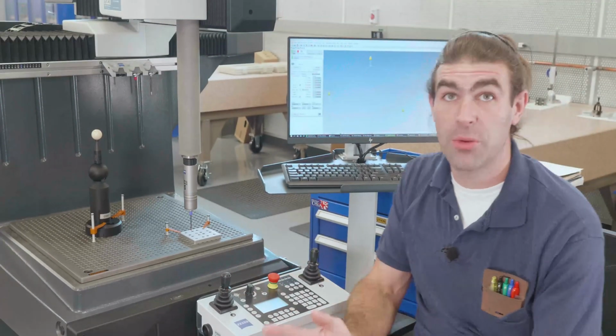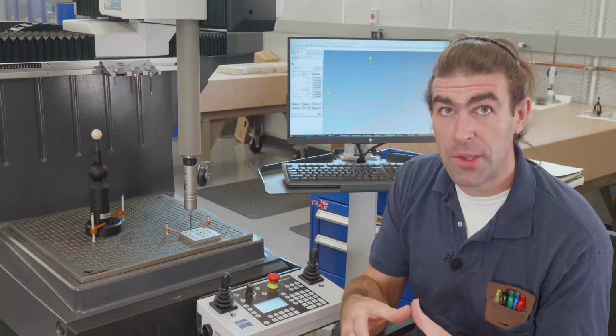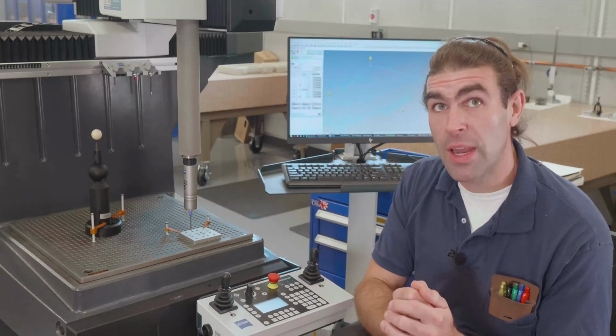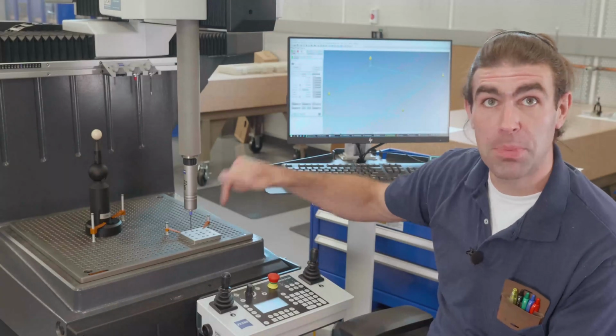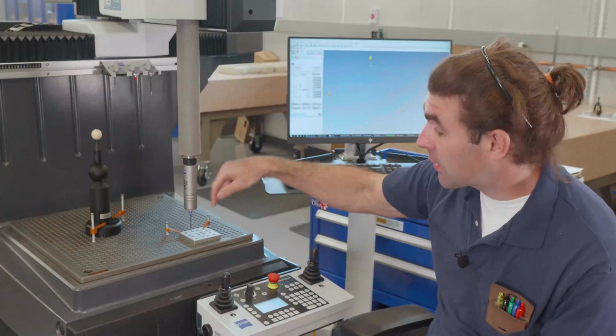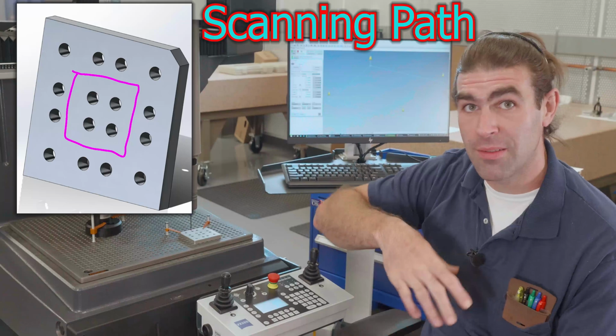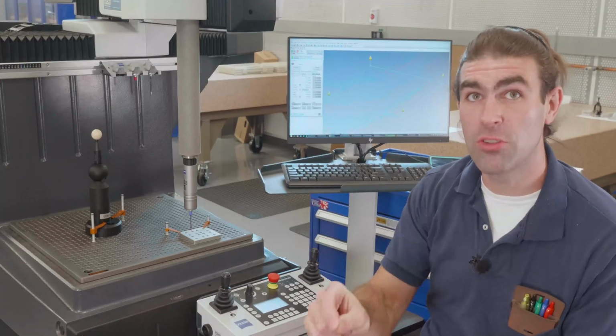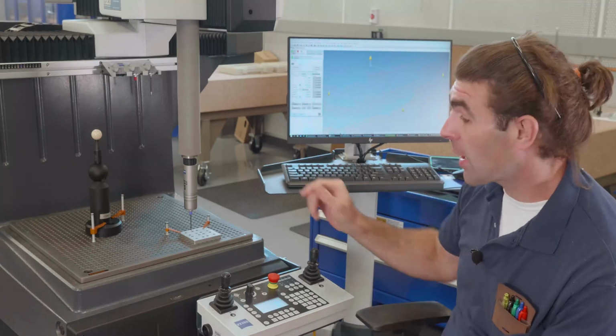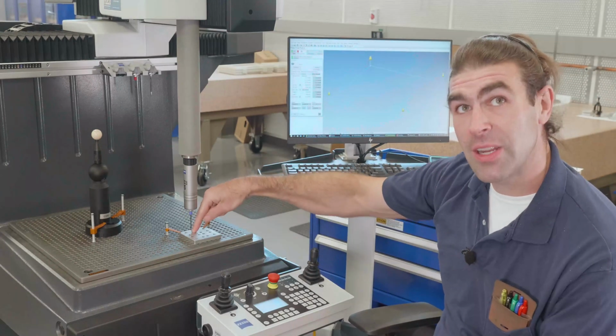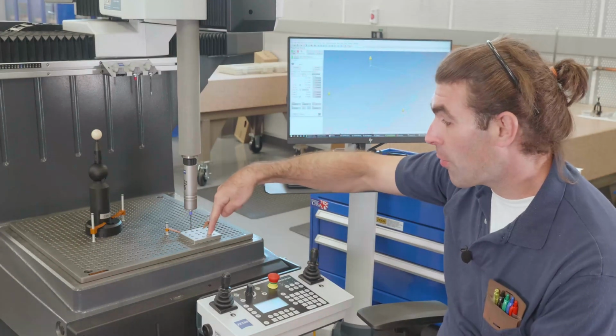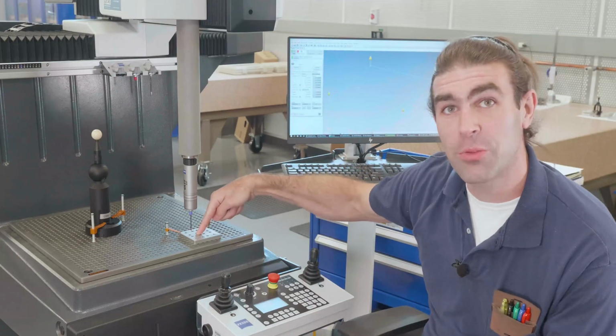So why did I do it in that particular way? Well, the machine is gonna default to what's known as scanning. So when it actually runs the program, it's not going to go beep, beep, beep and take four points. It's gonna drag the probe across the part. Now, what path does it take? It's gonna follow the points that you took. So you'll see when we run the program, it's gonna press down right here and it's gonna drag the probe to connect those dots.